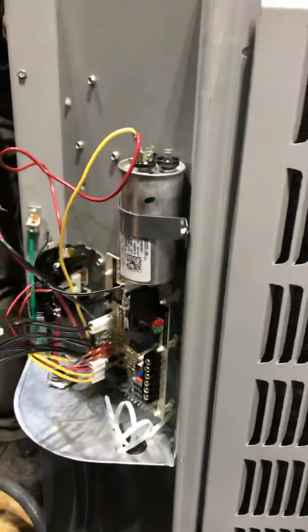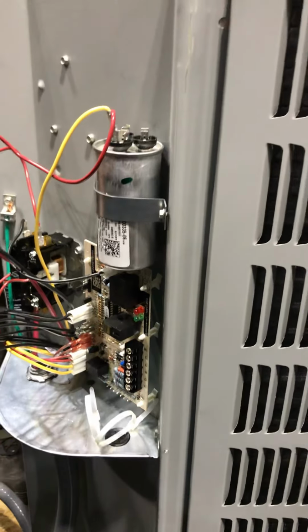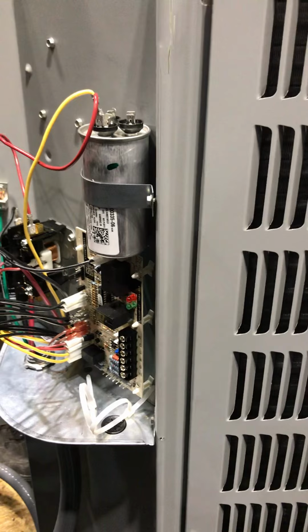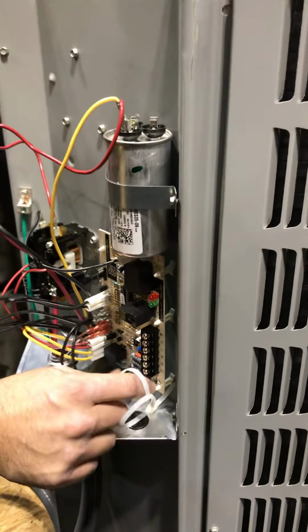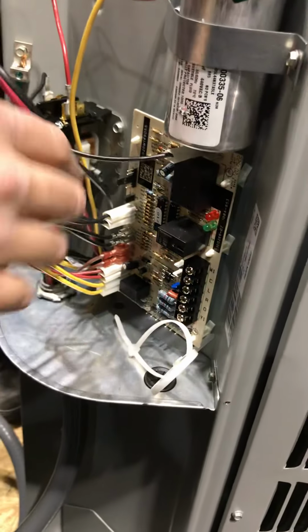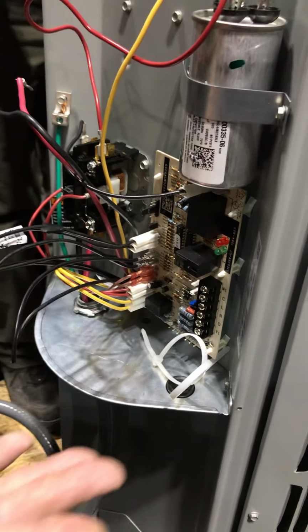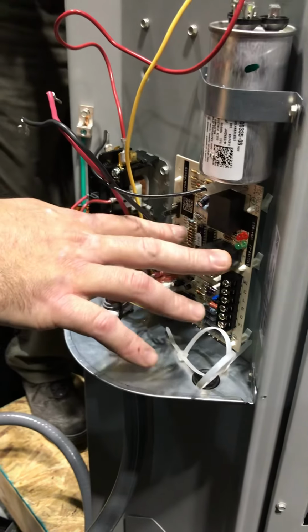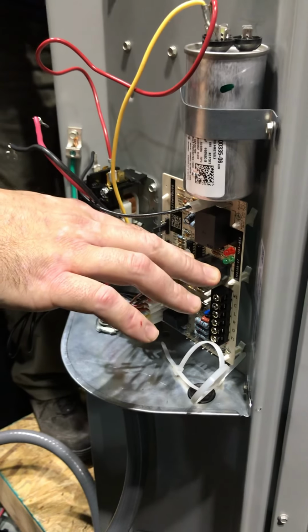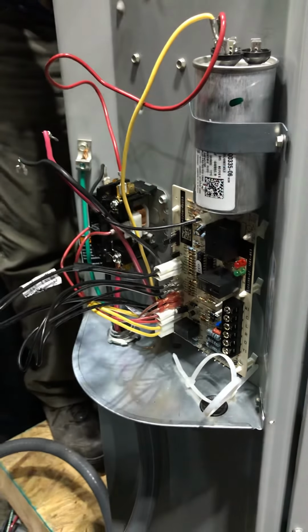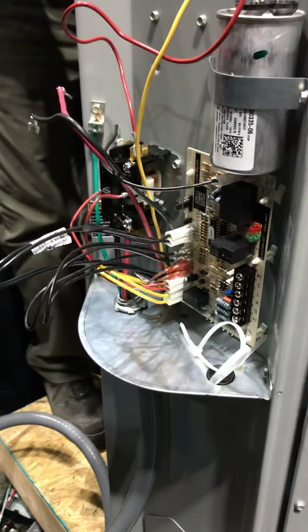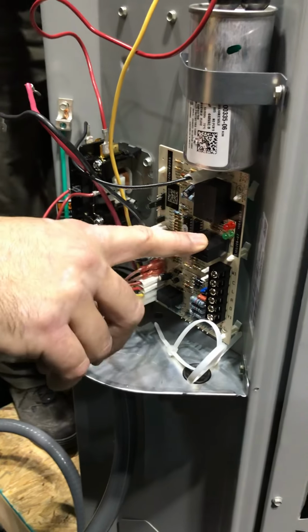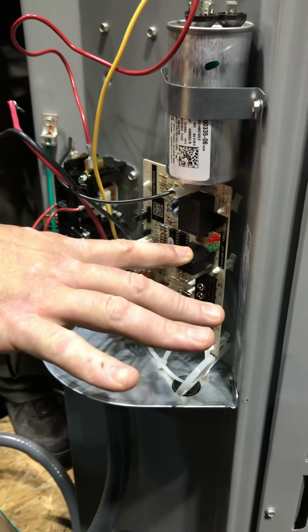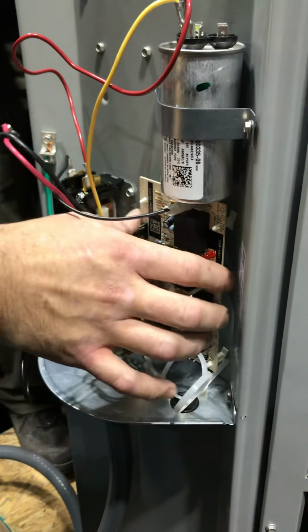Well, there are ways you can. You know how you plug that little micro machine into your car and it sends you a code? Yeah. They have those for these too. I can't afford one. They're hundreds of dollars. But that's where this thing comes in. I can plug this in, when this little light turns red, and it can tell me everything that's wrong with this. This is basically just communicating with my thermostat. And it's letting me know what's working and what's not working. And it gives power. This is only here because of the reversing valve. If this wasn't a heat pump, I normally wouldn't have these.